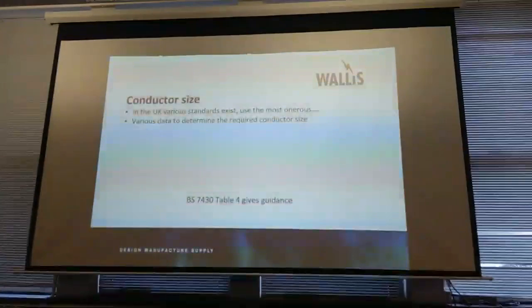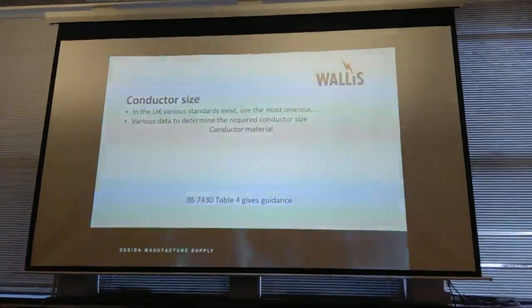UK standard, yeah, various data determine the conductor required. So we need to know what conductor material is used. Predominantly in the UK, it is copper. We are coming across more and more sites that are being built by, say, German companies or something like that, where they are trying to use galvanised steel in the ground as the main earthing system. It's fine, as long as it's rated, as long as it's sized correctly, as long as it's jointed correctly, fantastic. It's just an absolute pig to work with.